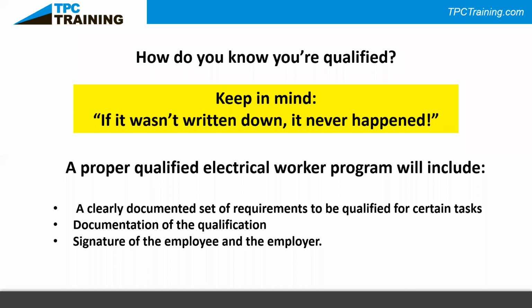A clearly documented set of requirements to be qualified for certain tasks. One thing you'll see in NFPA 70E is that you could be qualified to do one job but not qualified to do another. So you could be qualified by your employer to work on, let's say, 24-volt control circuits on your PLCs. But as soon as you open the cabinet to the motor controllers and motor starters at 480 volts, nope, you're not qualified to do that. We need someone else to do that.